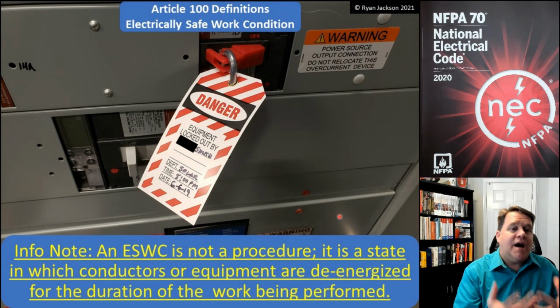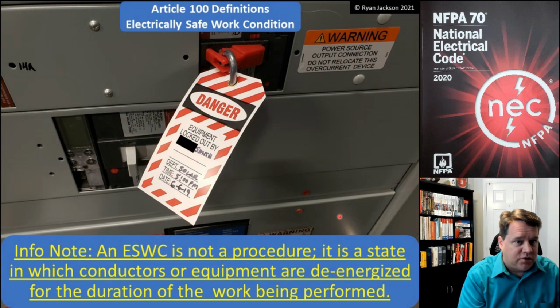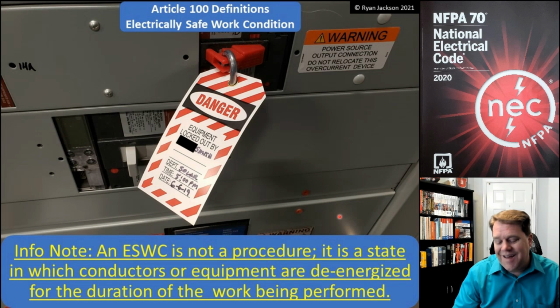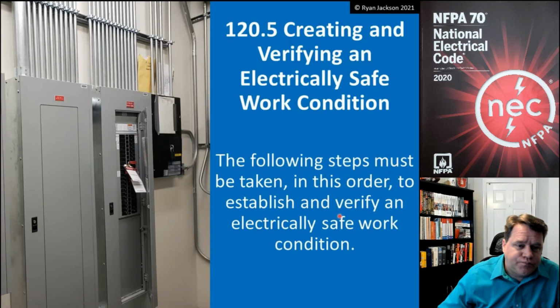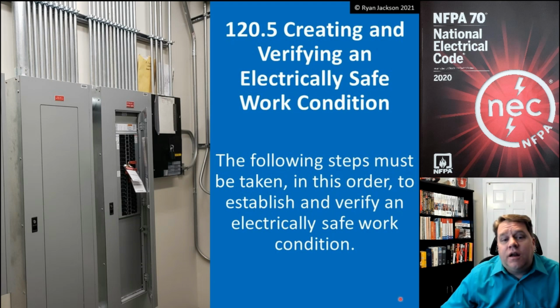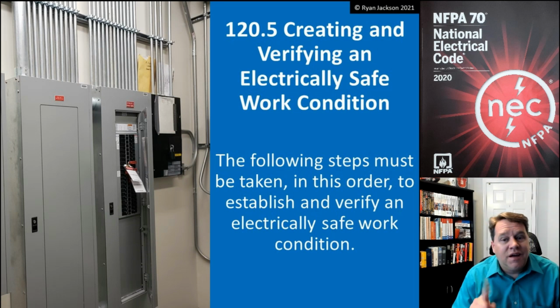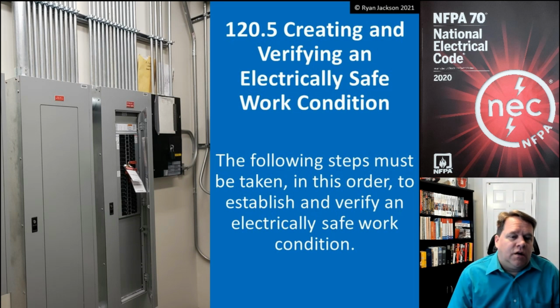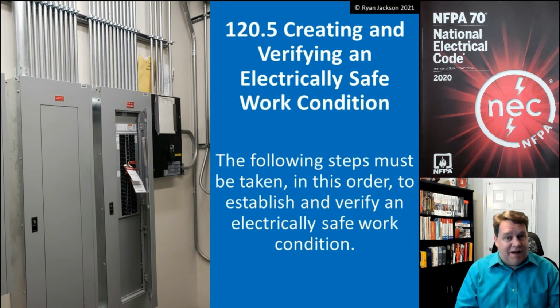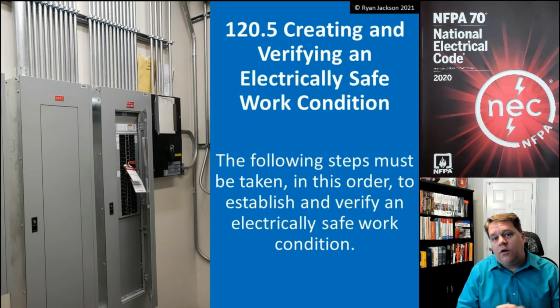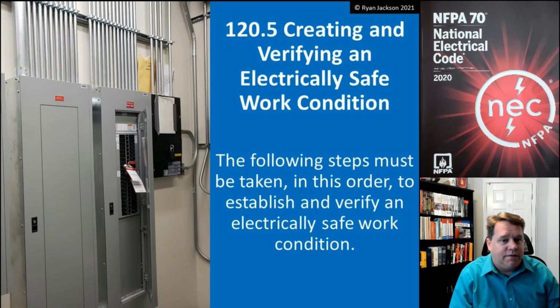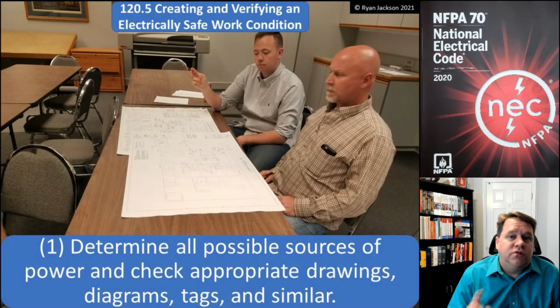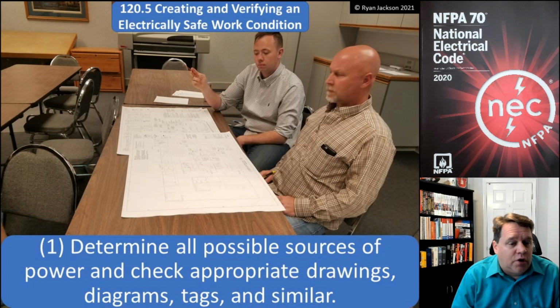So we're going to talk about how you actually create and verify the electrically safe work condition. That's kind of the emphasis of today's topic. So 120.5, creating and verifying an electrically safe work condition. Here's how you do it. The following steps must be taken in this order to establish and verify an electrically safe work condition. All right, so how do you eliminate the hazard, right? That's the name of the game. The first thing we want to do is eliminate the hazard, and that means we create and we verify the electrically safe work condition. So step number 1, determine all possible sources of power and check the appropriate drawings, diagrams, tags, and similar.